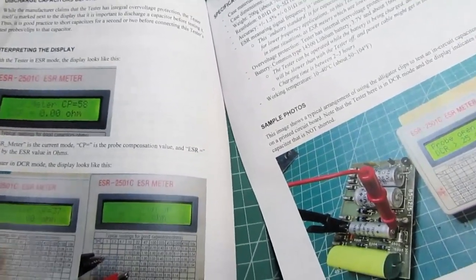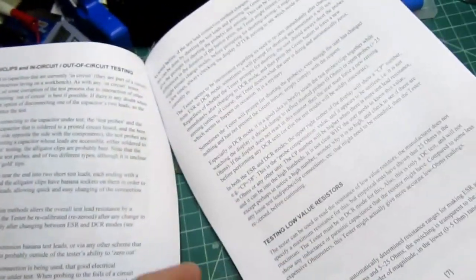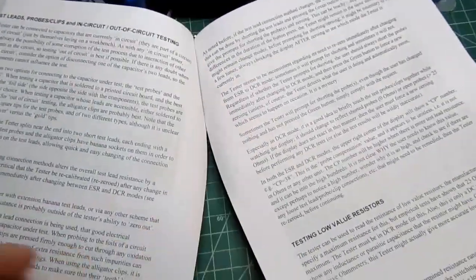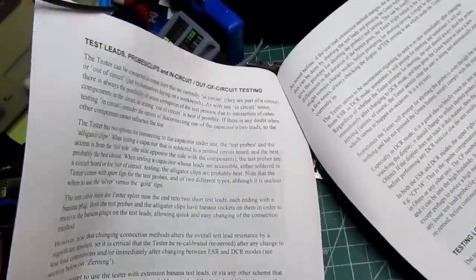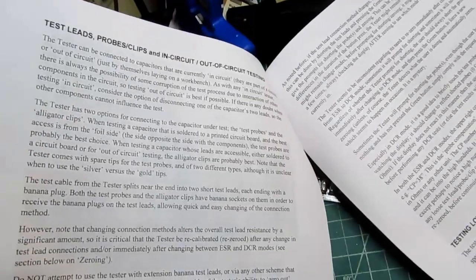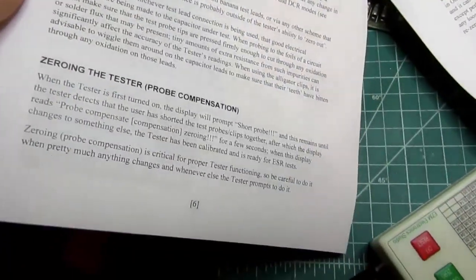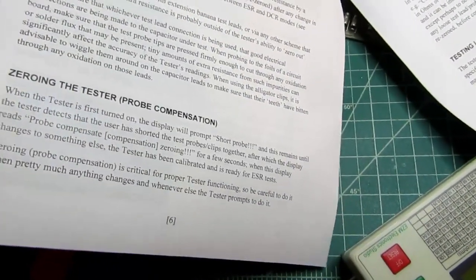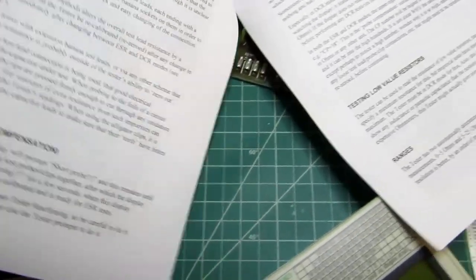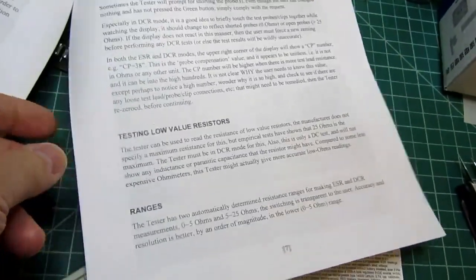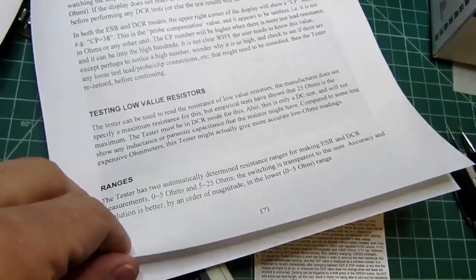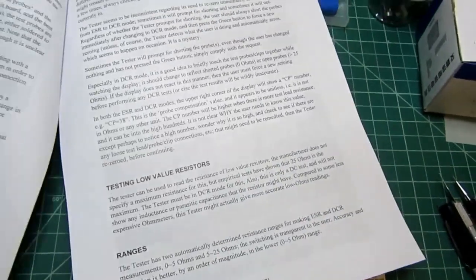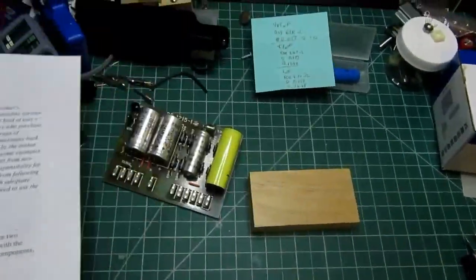There's a caveat about the best types of capacitors to use this tester with. It talks about how to change the modes, how to re-zero the probes, test leads, probe clips, in-circuit and out-of-circuit testing, zeroing the tester or probe compensation, testing of low-value resistors, and the two different ranges the tester can be in. So, ten pages of good stuff.